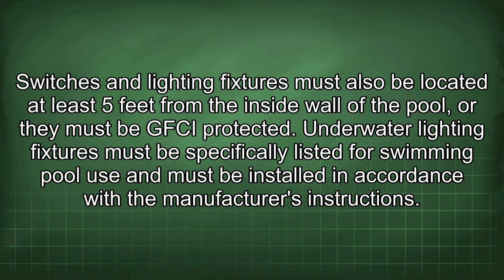Switches and lighting fixtures must also be located at least 5 feet from the inside wall of the pool, or they must be GFCI protected.